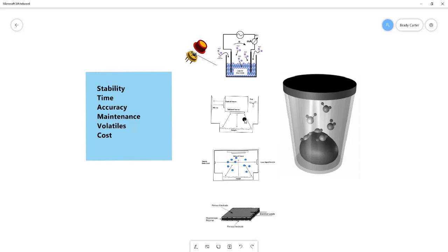But then with the chilled mirror, the problem with the dew point is that when the mirror is chilled, there will be volatiles that will co-condense on the mirror, and they will impact subsequent readings. And there's really no way to avoid that. So this particular one, the only choice when you have volatiles present, and they're specific volatiles, but if they are present, the only choice is to not use the sensor.